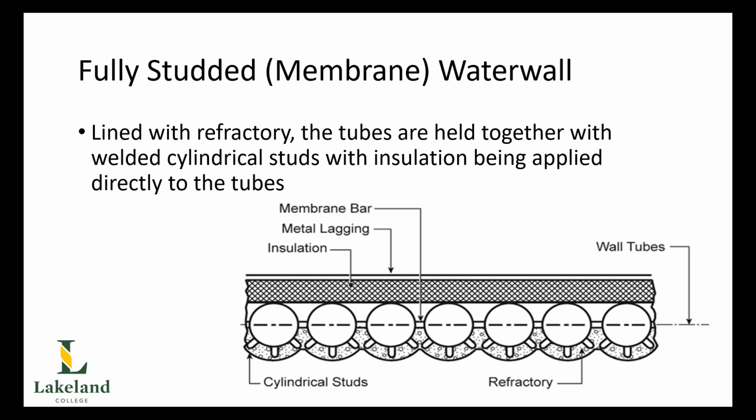And this was a refractory layer coated on the outside of Inconel tubes to protect the tubes from corrosive gases of the refuse being burned. So that was a typical example there. And the refractory that we used in that example was a silicon carbide refractory. So this fully studded just refers to the pin studs over those tubes that the refractory can be attached to.